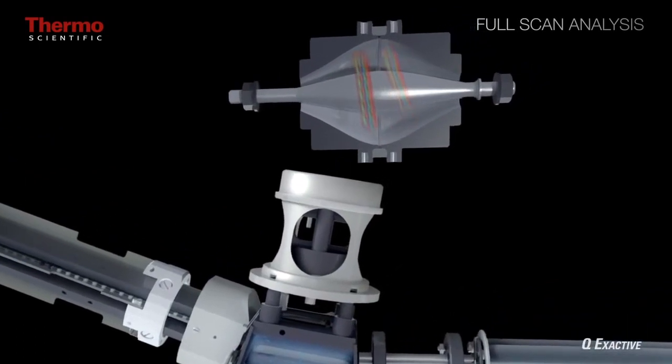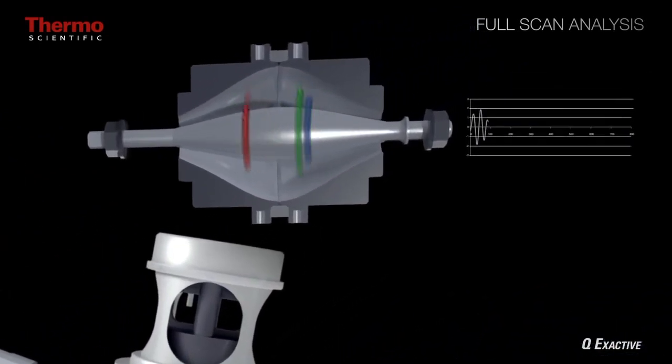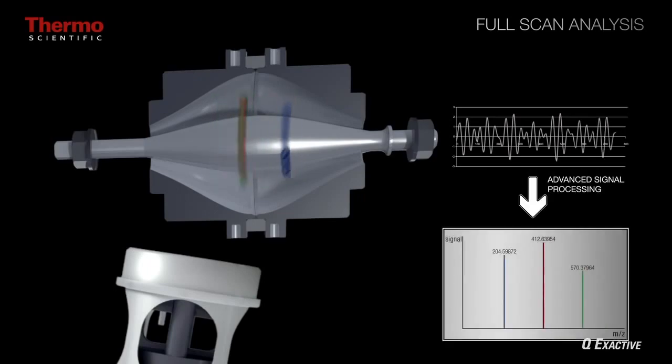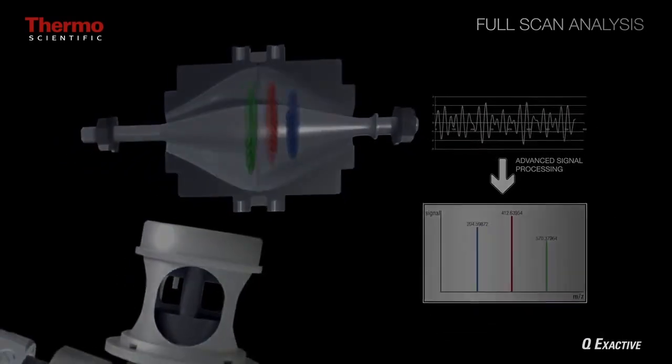In the orbitrap, ions are trapped in an orbital motion where the frequency of rotation is related to the mass-to-charge ratio. Therefore, ions with different mass-to-charge ratios will have different frequencies of oscillation.